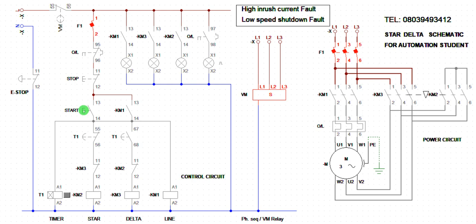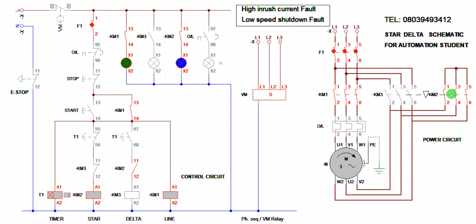Let's simulate. I put on the operation — the line contactor and star contactor are now on, the motor is running. After a few seconds, the delta takes over: the star gets disengaged and the delta gets energized. The motor is now running on high speed. The system is working correctly.